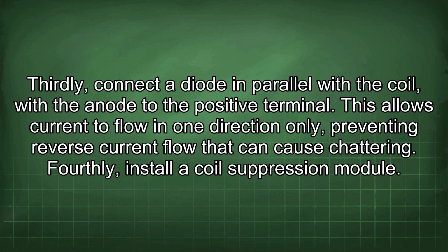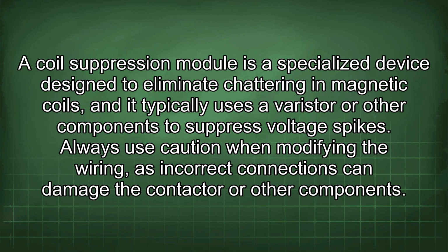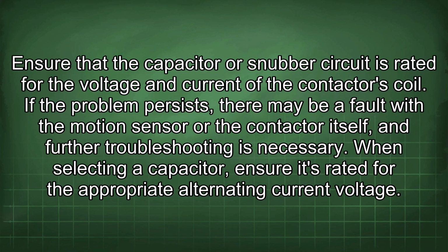Fourthly, install a coil suppression module. A coil suppression module is a specialized device designed to eliminate chattering in magnetic coils, and it typically uses a varistor or other components to suppress voltage spikes. Always use caution when modifying the wiring, as incorrect connections can damage the contactor or other components. Ensure that the capacitor or snubber circuit is rated for the voltage and current of the contactor's coil.